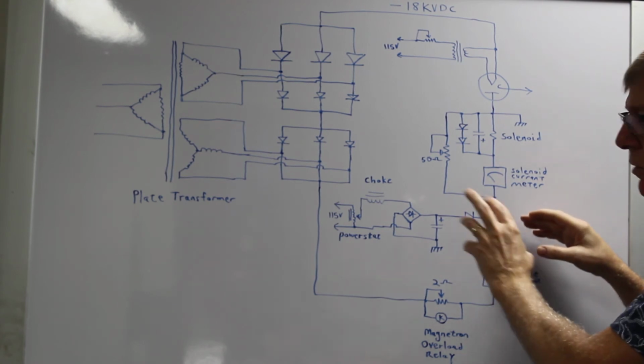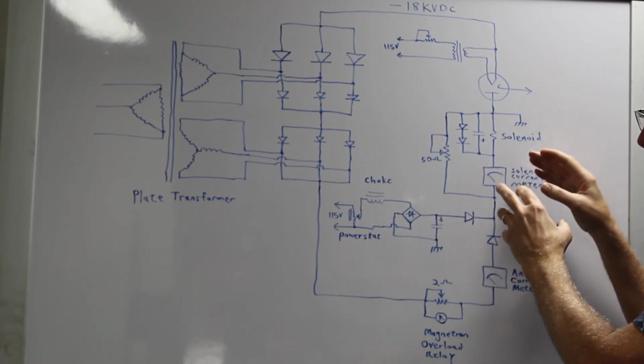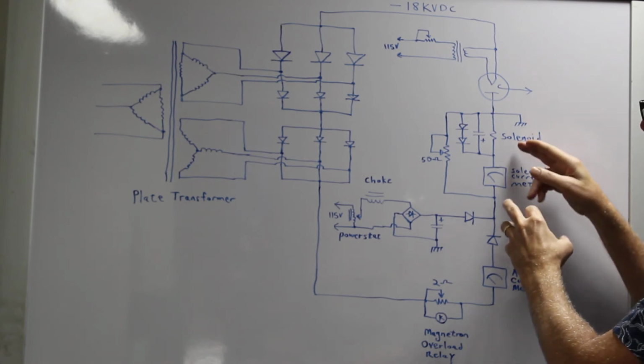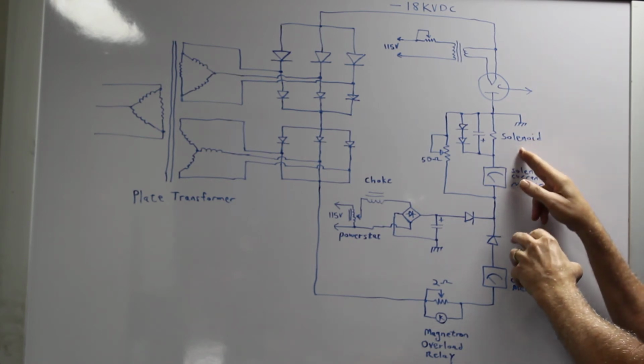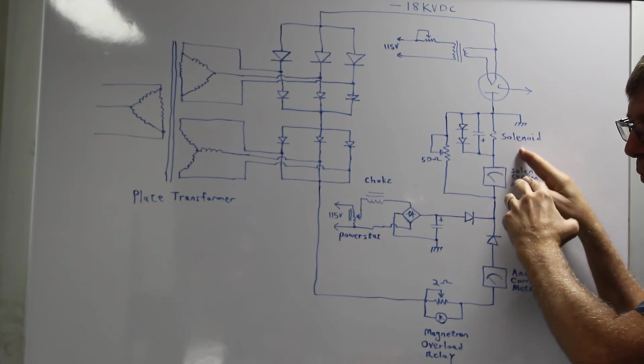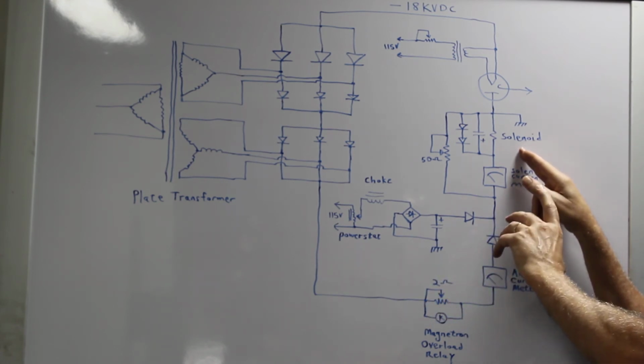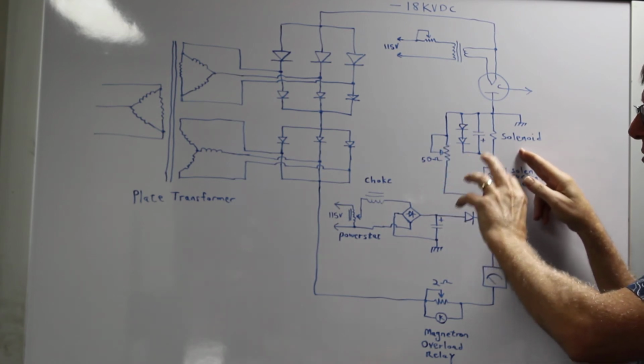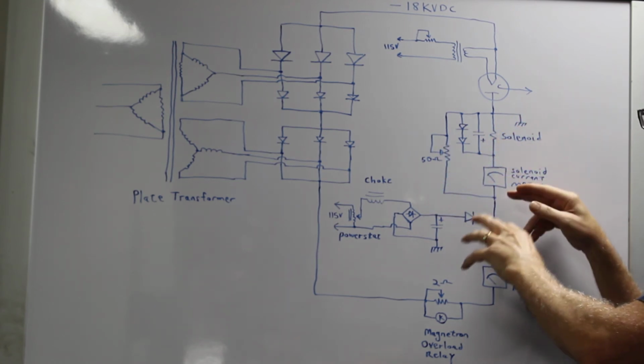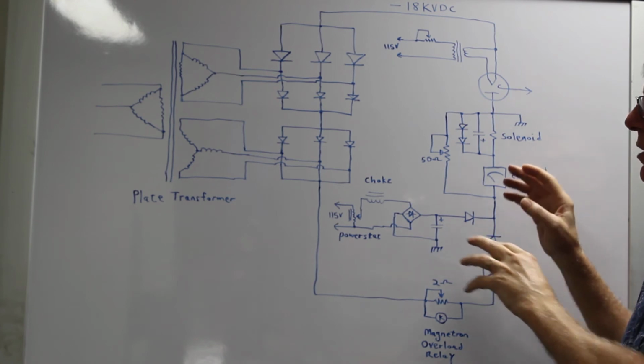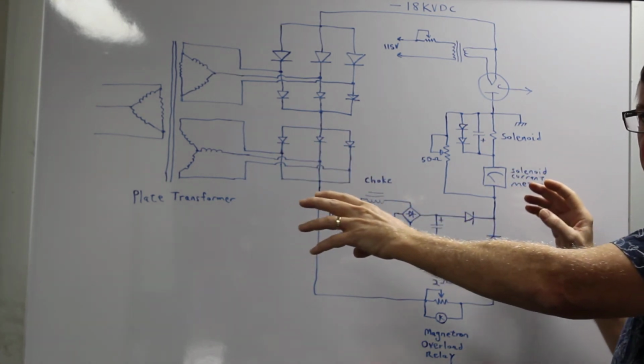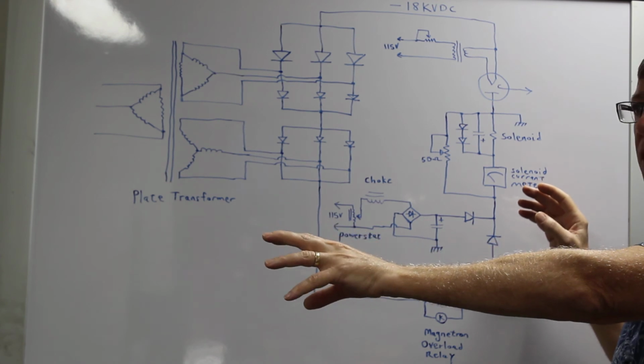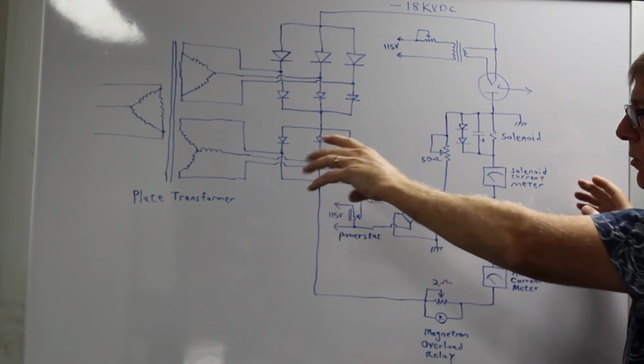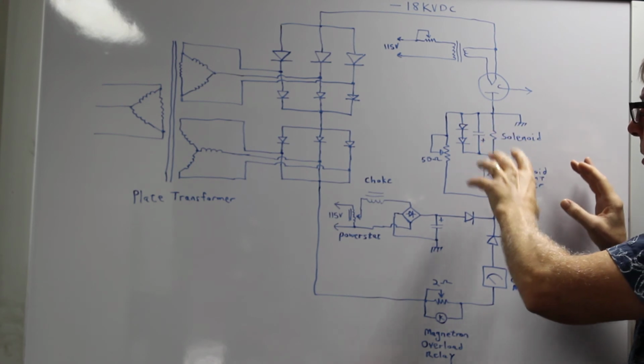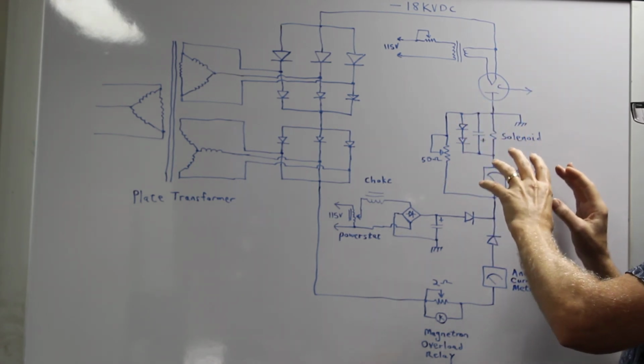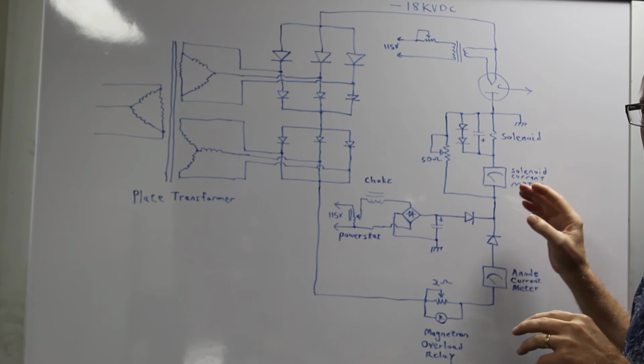So as we increase the RF power and the anode current rises, it generates an additional magnetic field in the solenoid, which is contrary to our reduction of the solenoid current to increase the power. And that means that as the RF power goes up, it will attempt to reduce the RF power. The purpose for this is so that if the power mains in your building fluctuate from other large machinery turning on or off, or some other perturbation that would tend to affect the RF power, this feedback circuit will effectively minimize that power fluctuation.